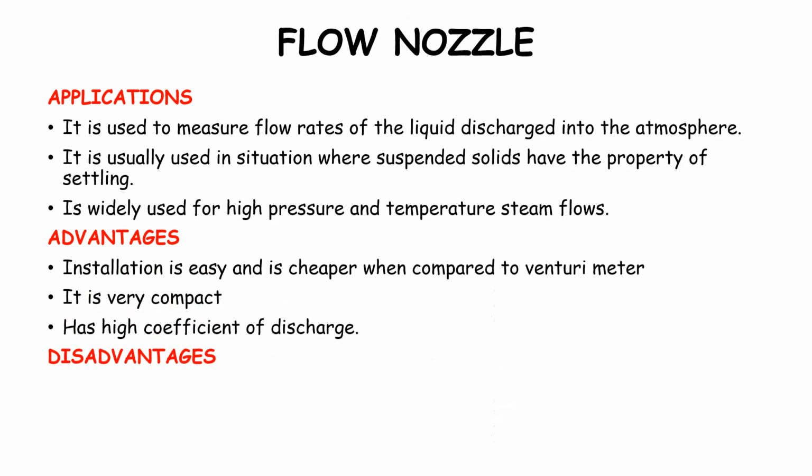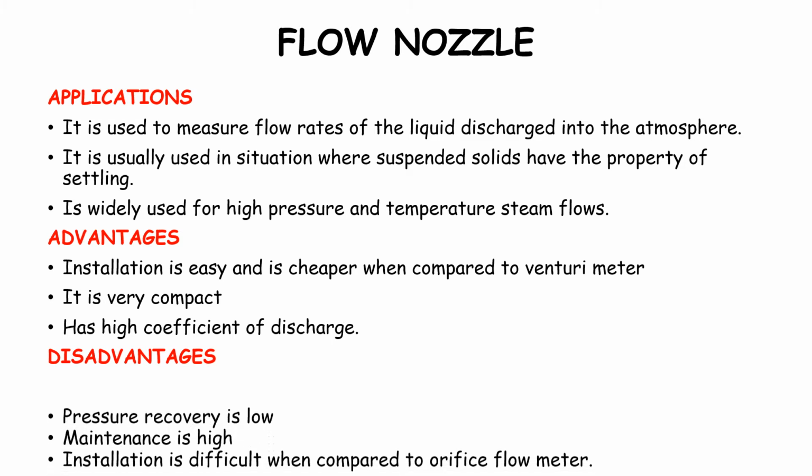Moving on to the applications, it is used to measure flow rates of liquid discharged into the atmosphere. It is usually used in situations where suspended solids have a property of settling, and is widely used for high pressure and temperature steam flows. Into the advantages, the installation is easy and it's cheaper compared to the Venturi meter. It is very compact and also has a high coefficient of discharge.